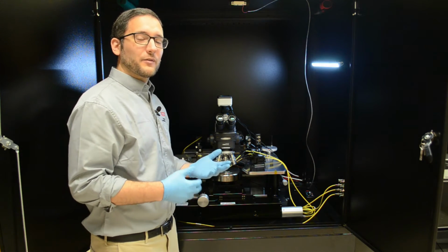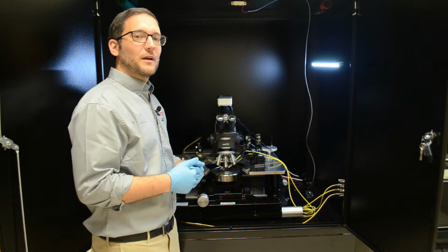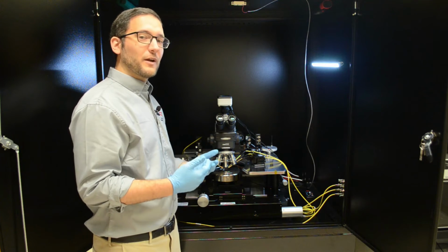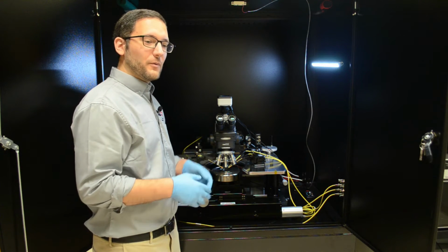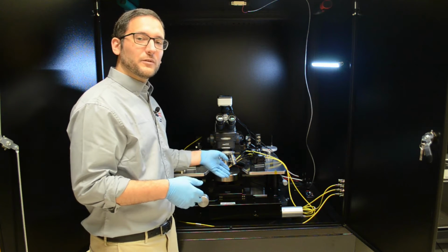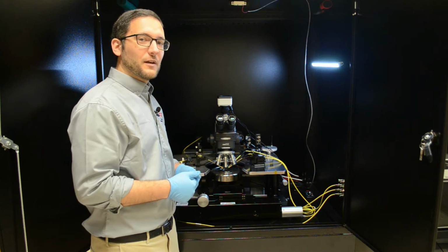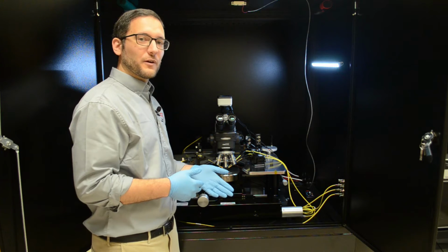Micro because they allow us to have micrometer precision over the movement, and positioners because we are trying to position a probe. A probe is a needle with a very fine tip. It's a metallic needle which will touch down or probe the device. And it's through that probe that we apply voltages and measure currents, for example.